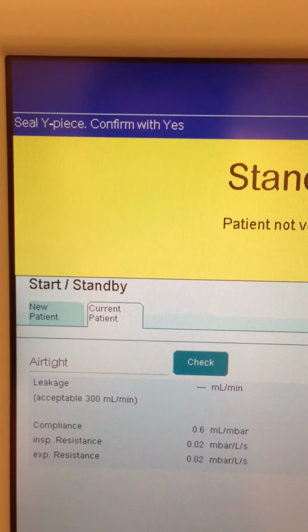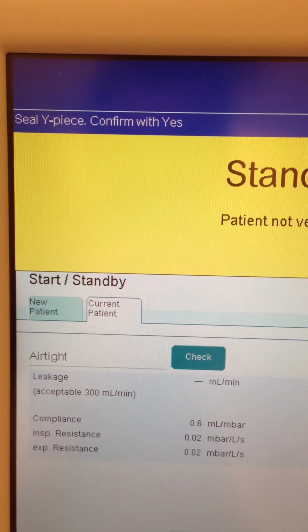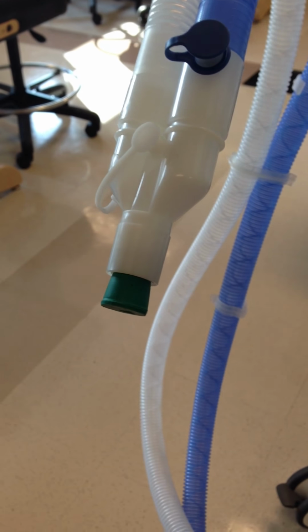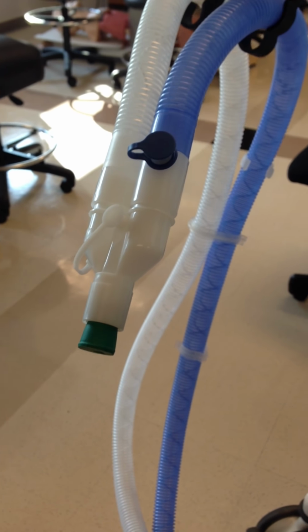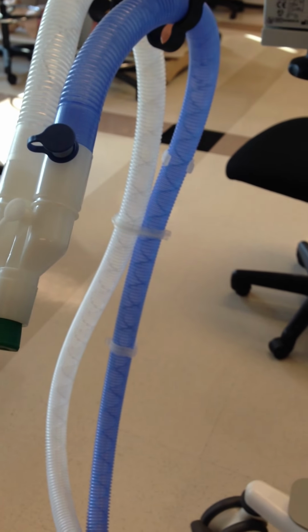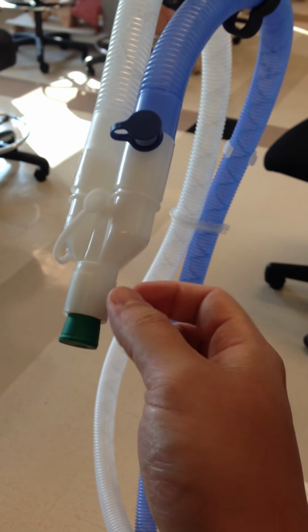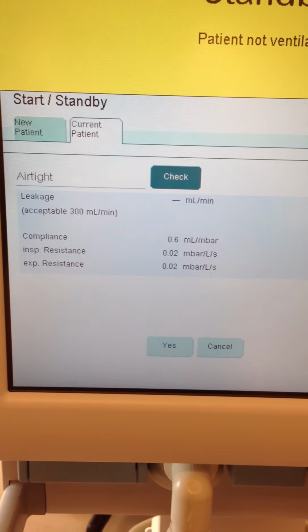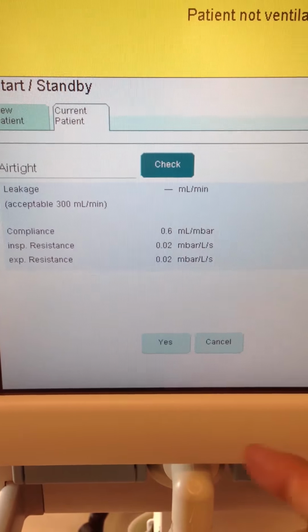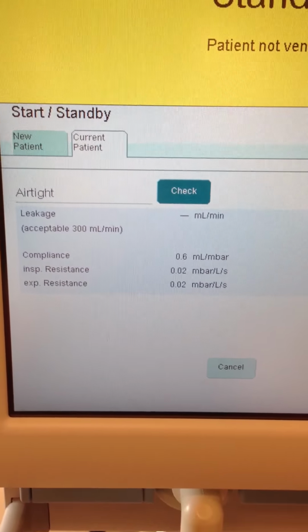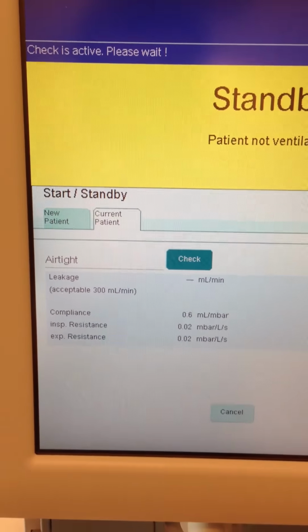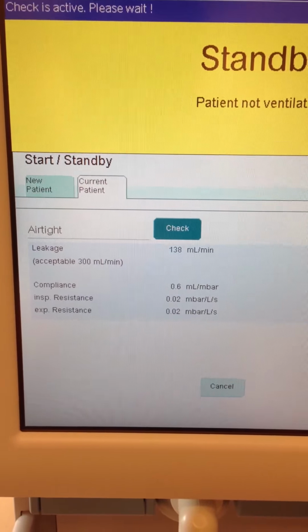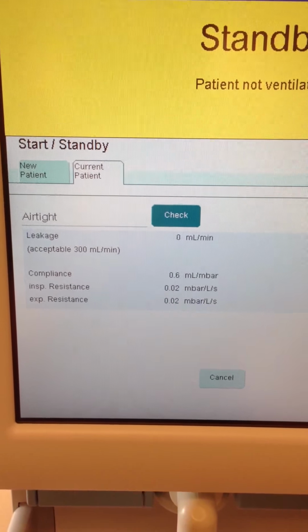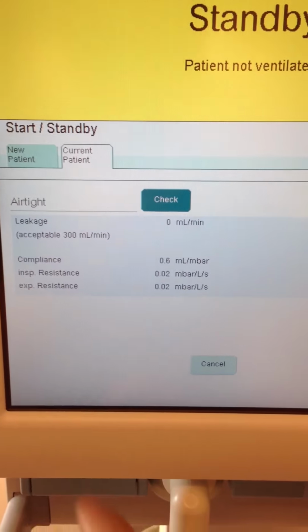It says seal the Y piece and confirm with yes. So I've just stuck a plug into our circuit. One nice thing about these circuits is when you open up the package, usually they come with a blue cap. Keep that blue cap because it'll help you with these tests so that you can free up your hands by keeping that cap on. So now I'm going to just go ahead and hit yes. It's sealed. Check is now active. You're going to hear the ventilator cycle on and off and pressurize the circuit. We're looking for a leak that's under 300 mils per minute, as you can see here.